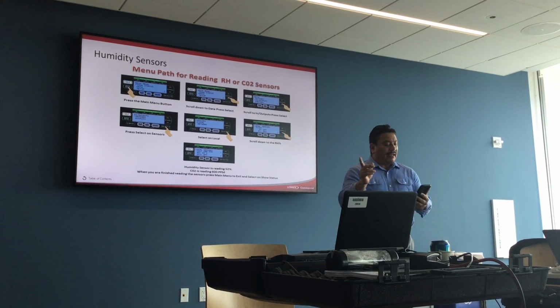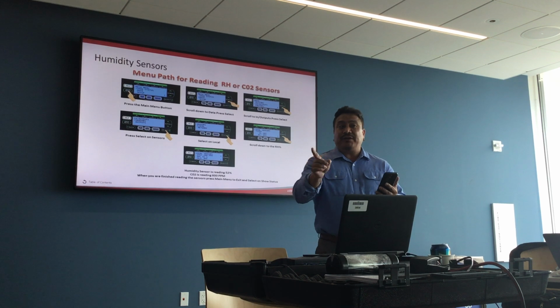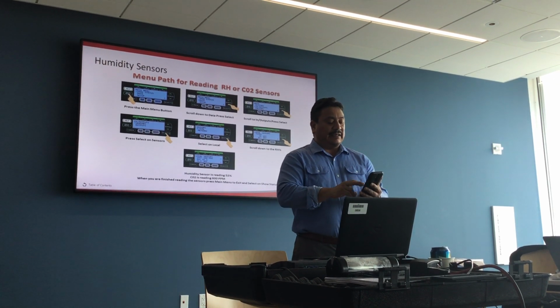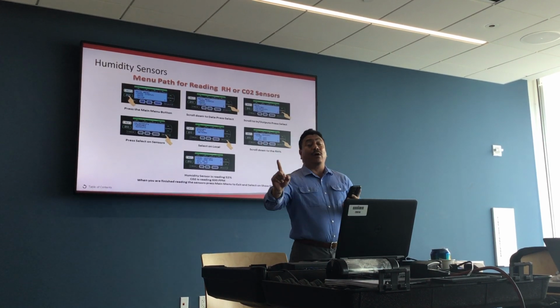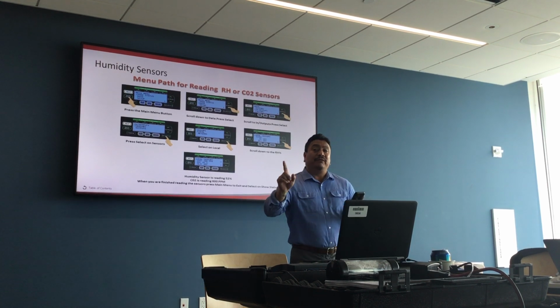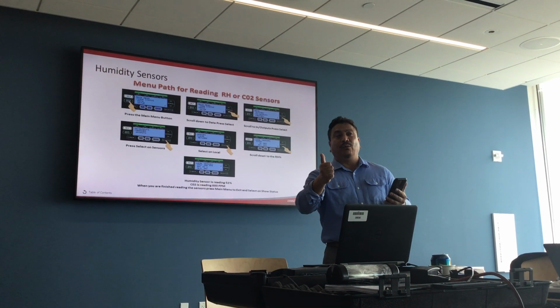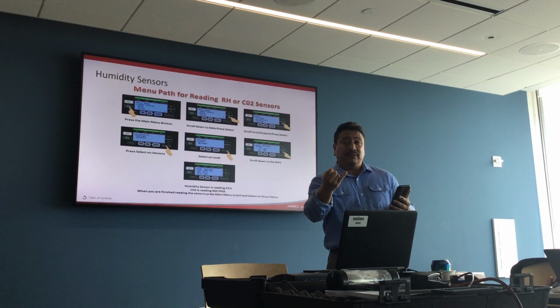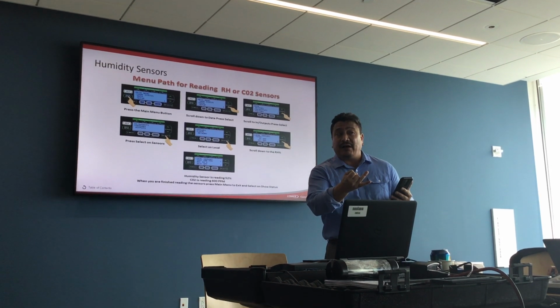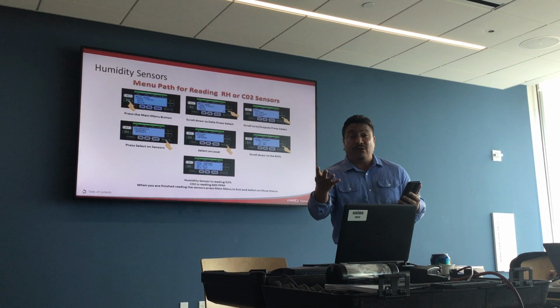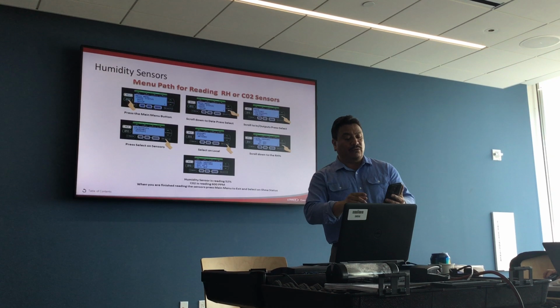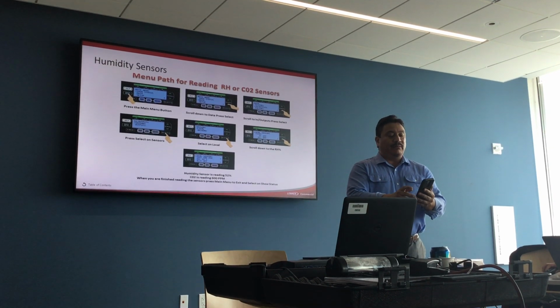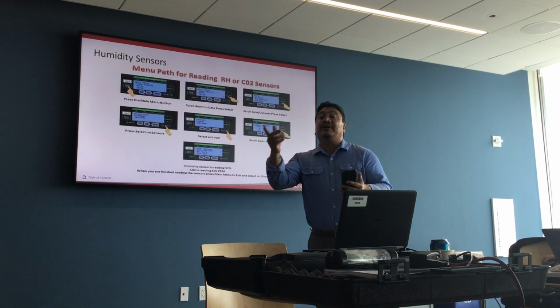Now, remember we talked about configuration ID? Check this out. So tap look up configuration ID. And it asks you, is this for configuration ID 1 or 2? Now remember, configuration 1 basically told the unit what? Whether it's got Humiditrol, economizer, type of economizer, power exhaust, the control of the power exhaust, okay? And so forth and so forth and so forth, right? So let's go ahead and click configuration ID number 1. And I'm going to give you some parameters.